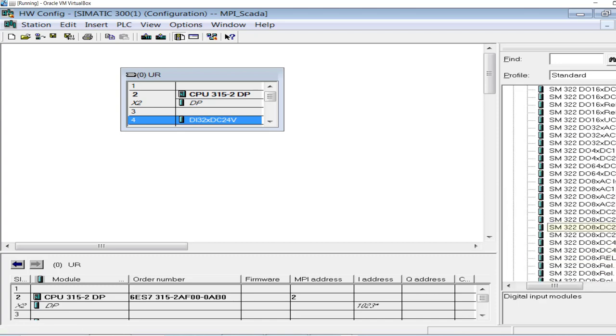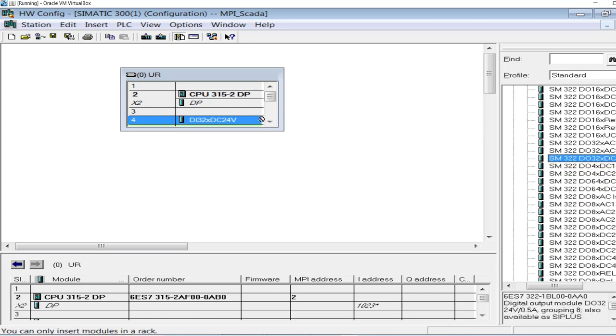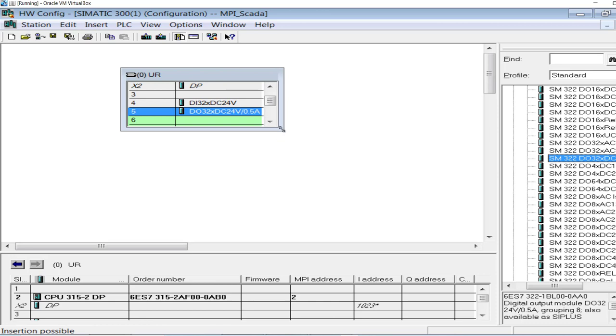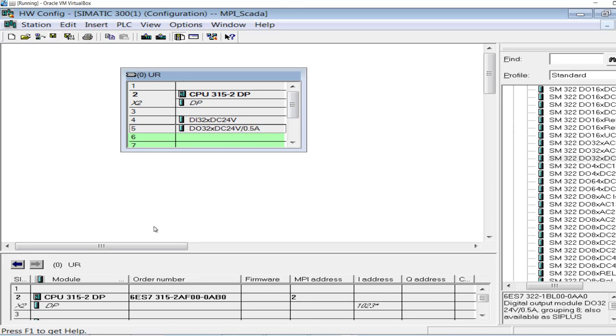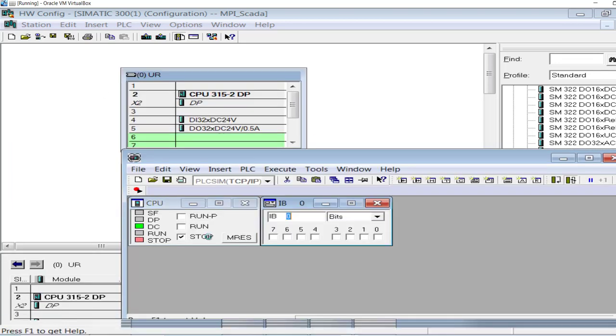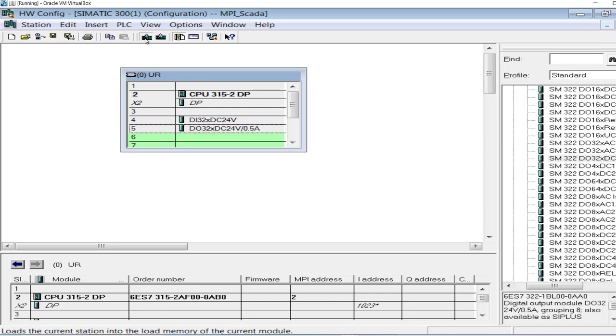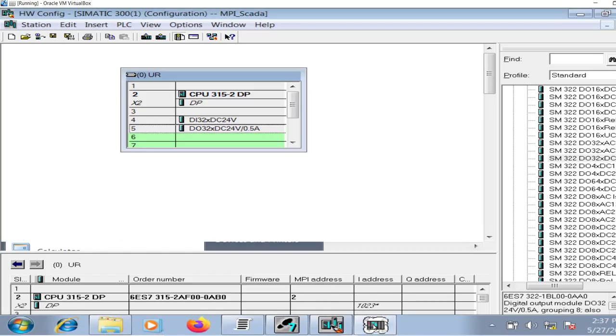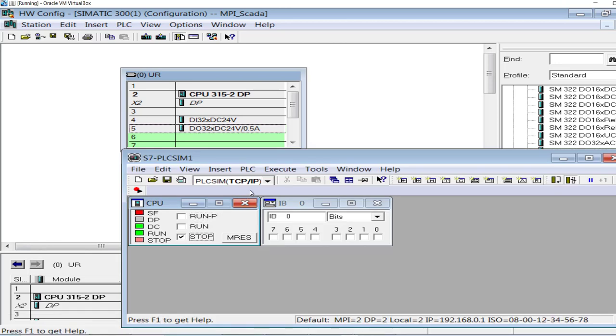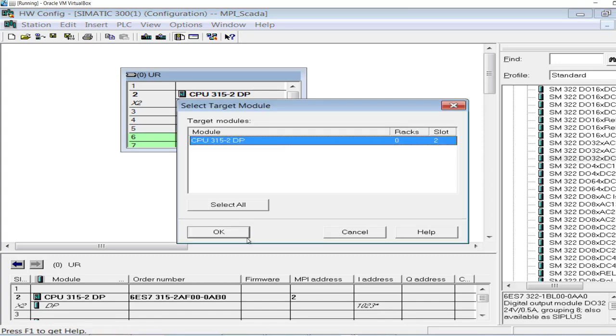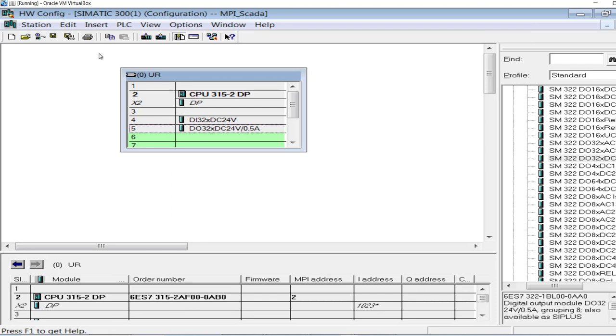My hardware configuration is now complete. I will save the project, and instead of a physical PLC I'll be using a simulator — the process is the same for both. Place the PLC to stop mode and download the project. Note: the interface is not TCP/IP, it's the MPI interface. Get the PLC to stop mode again and download the hardware configuration to the CPU. Now I'm done with the hardware settings.